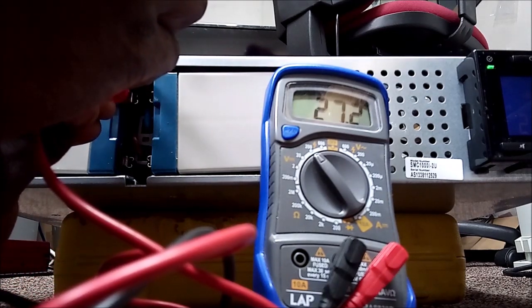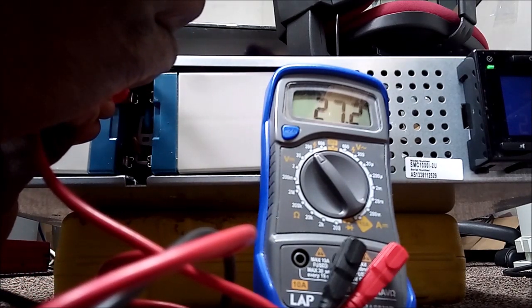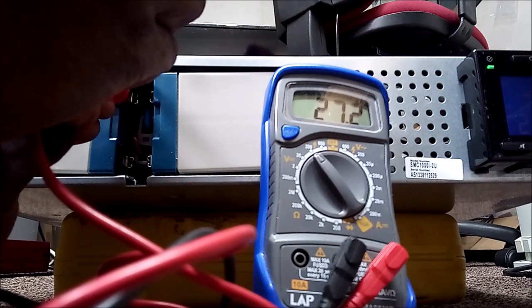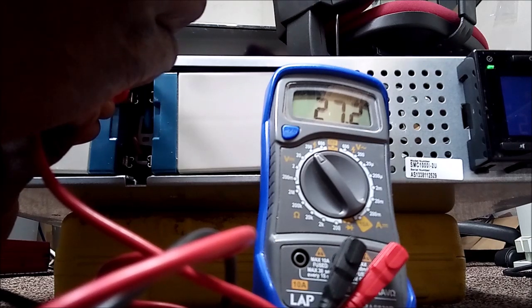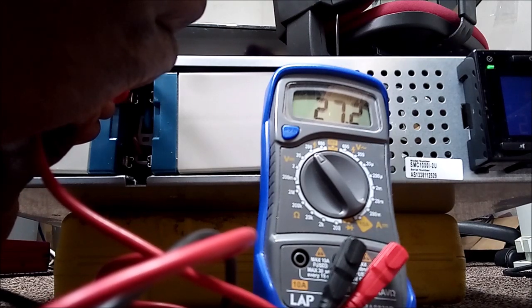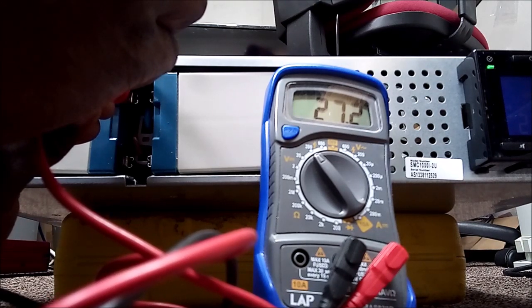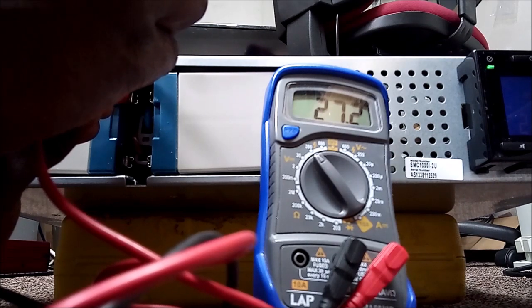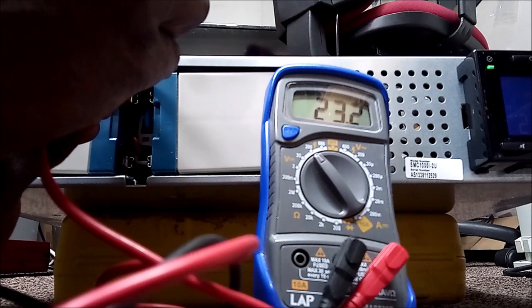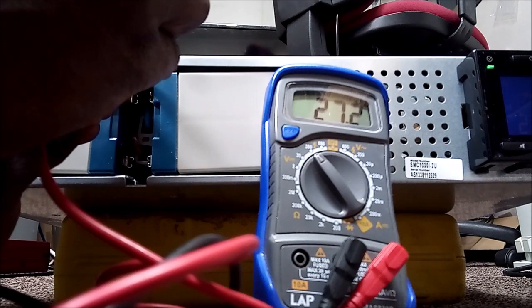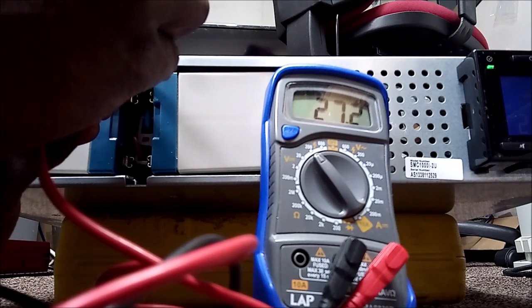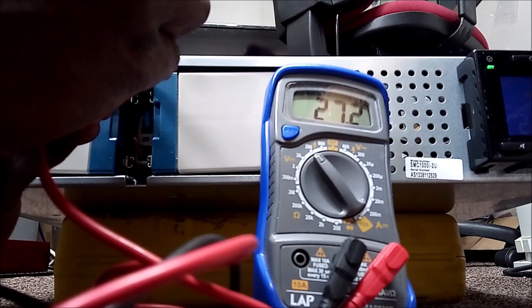And as you can see, it's reading 27.2, so that is already above 24 volts. That's an indication that it's charging at 27.2 volts. That is how you tell if the charger in this UPS is charging your battery.